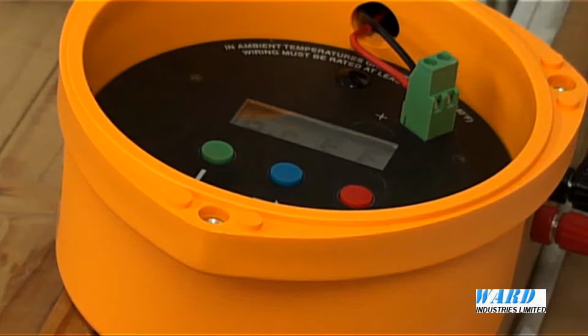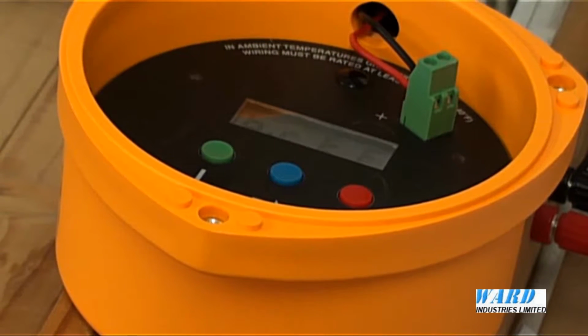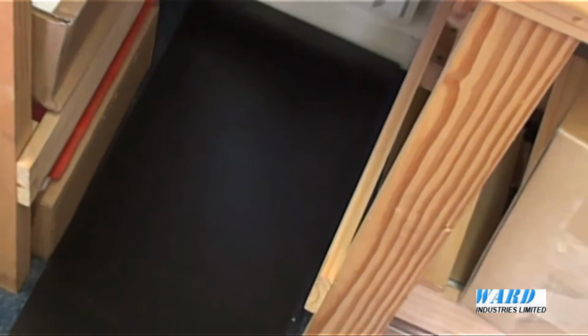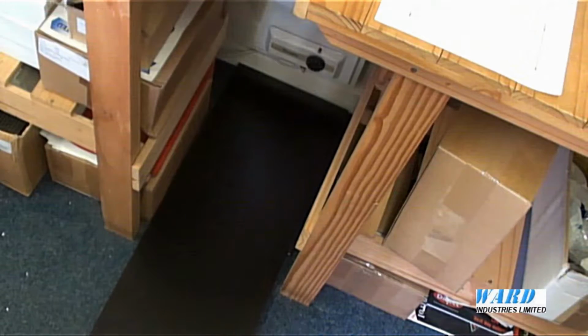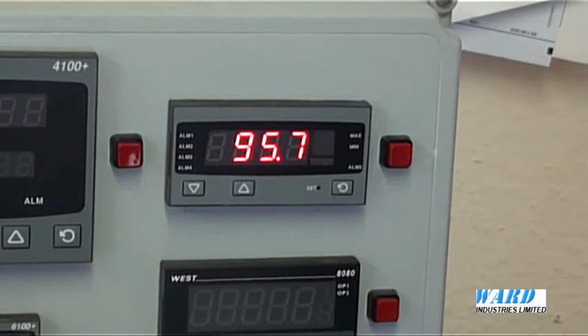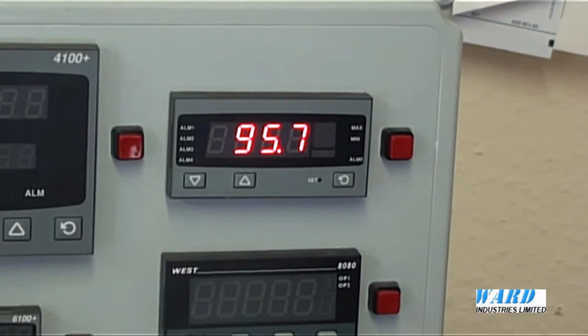Now let's assume in this example we have a tank with a bottom reference, i.e. from the transmitter face to the bottom of the tank, of 1 meter. Now here on the floor I have a board to simulate the liquid level in the tank. I also have the transmitter connected to a digital indicator. The digital indicator is programmed to have a scale of 0 to 100% for an input signal of 4 to 20 milliamps. So we need to change the factory default value of Bref from 8 meters to 1 meter.